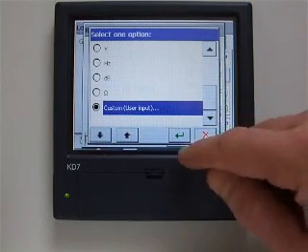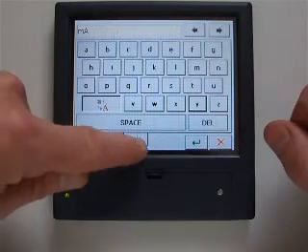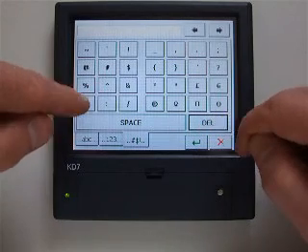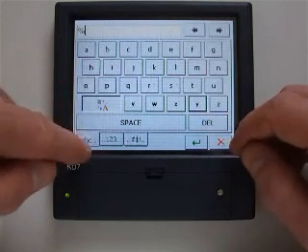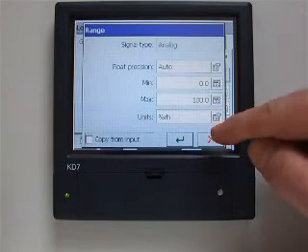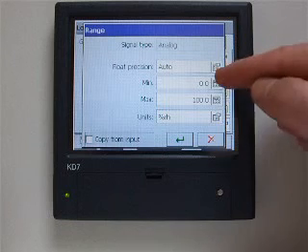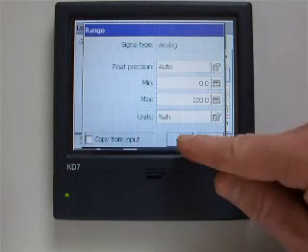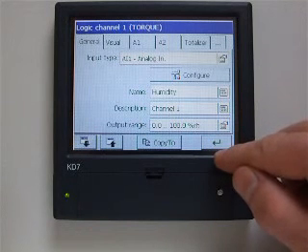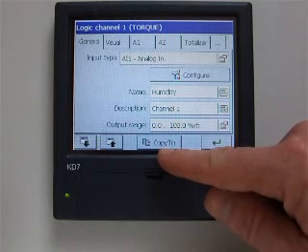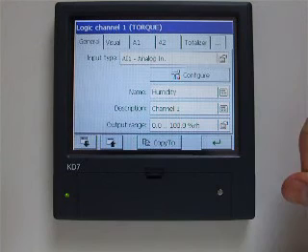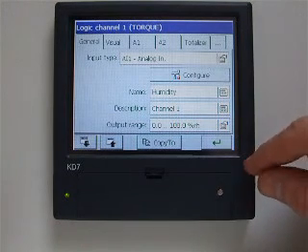So what I'll do is choose the custom input code for that, and using my special characters on the keyboard here, I can choose percent, let's just get rid of the milliamps at the moment, percentage, and then I can call that RH for relative humidity, and enter. There we go, now we've got our units. So it's 4 to 20 in is 0 to 100 relative humidity percentage, and I can say OK. So very simple, very nice, easy system to set your inputs. And again, if I had multiple channels of this type of setting, I can copy these settings to all the other channels. So it reduces the amount of work that we need to do.